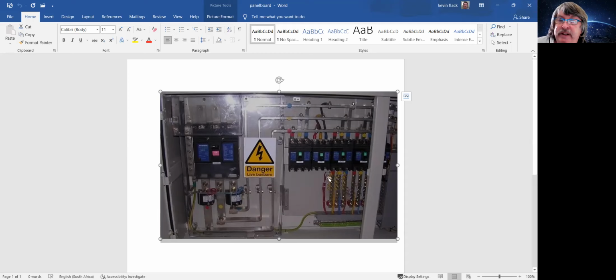And if we've got very low currents here, this breaker, say, has a 250 amp rating versus a 20 amp supply, maybe a lighting or plug circuit, and you're going to have cables going down here at 20 amps. Again, these cables may not be protected fully by the upstream breaker. They might be; I mean, a 250 amp breaker is not going to trip at 250 amps. This cable going to a 20 amp breaker could be legally anything from 2.5 to possibly 6 millimeters squared. And 6 millimeters squared is not going to take 250 amps, or let's say above 250 amps plus 35%, before this breaker trips. So that cable is going to get super hot. It's going to get damaged. It can fuse off.